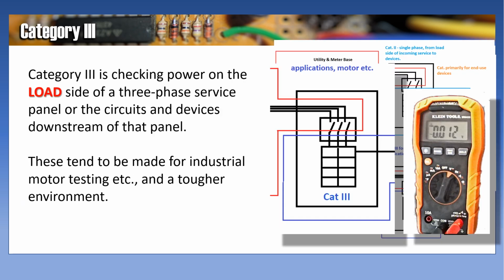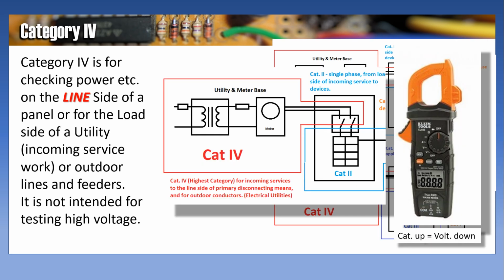Category 3 is checking power on the load side of a three-phase service or the circuits and devices downstream of that panel. These tend to be made for industrial motor testing, etc., and a tougher environment. Category 4 is for checking power, etc., on the line side of a panel or for the load side of a utility incoming service. It's also used for outdoor lines and feeders. It is not intended to be checking high voltage.